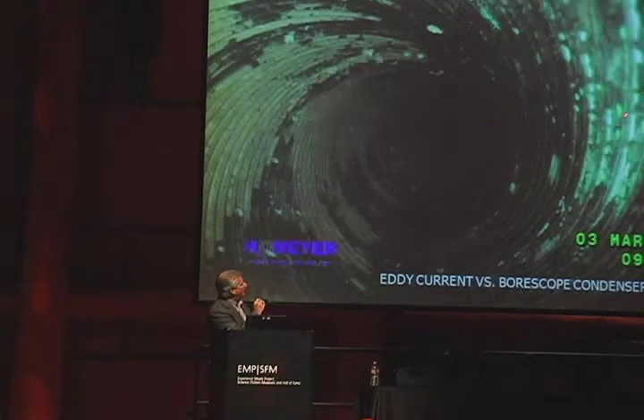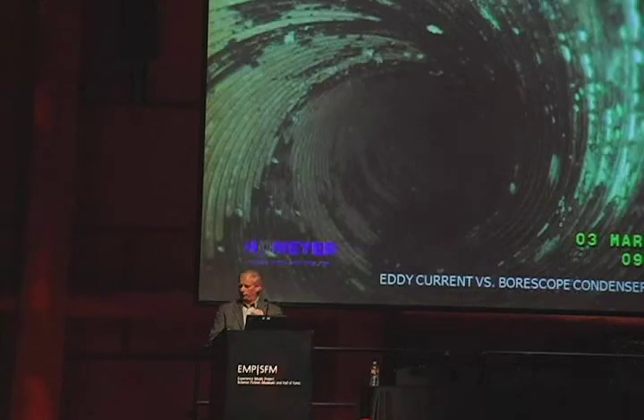We're seeing a little bit of copper corrosion over here. The green is actually copper oxide, and we're starting to see a little bit of scale formation on top of the tubes. If you were to run an eddy current, which they did on this plant, an eddy current study down there, which is basically determining the thickness of the tubes, the eddy current showed that this tube was fine. There was no problems, no defects in this tube.